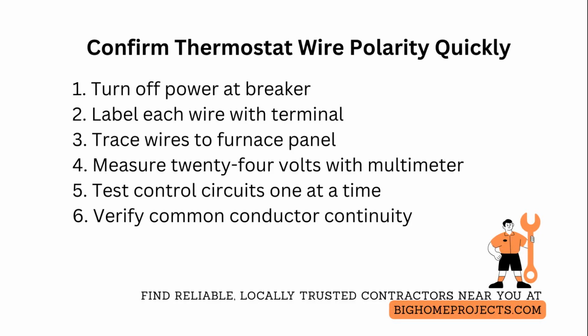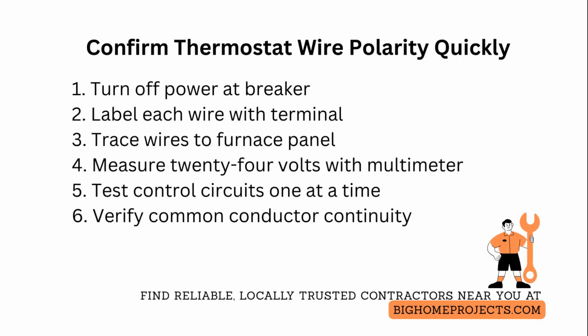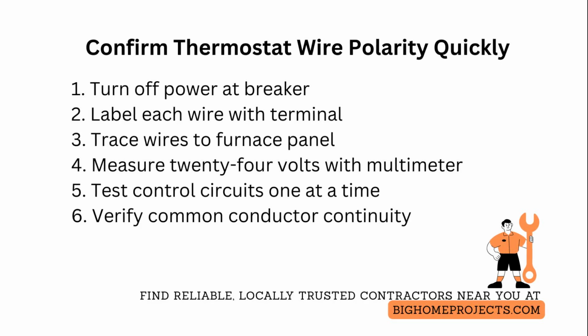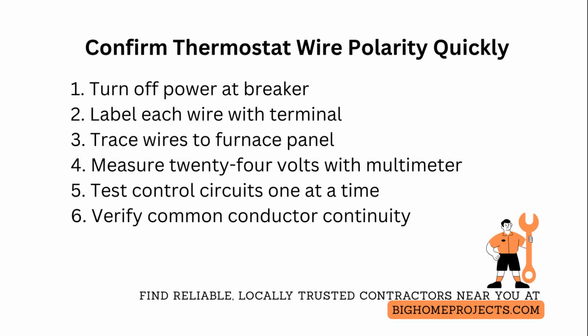If the old installer mixed colors, the labels become your source of truth. Next, trace the wires visually as far as you can toward the furnace or air handler. If they disappear into a wall, open the furnace low voltage terminal strip panel and identify which conductor lands where, writing those terminal letters beside your labeled conductors.